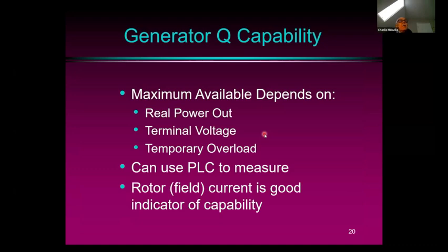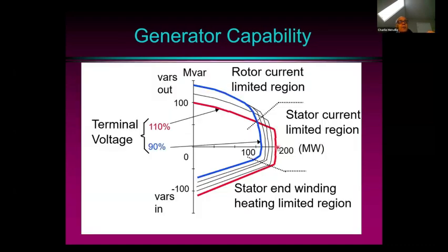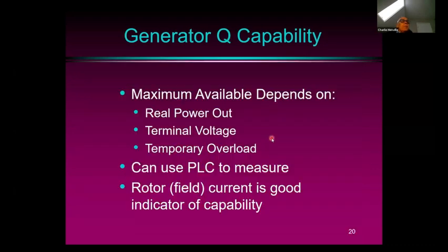So the maximum generator capability available depends on the real power output, as we saw previously. The higher the real power output, the less reactive power you can put out. It also depends on the terminal voltage, as I mentioned previously, and it usually has some temporary overload capacity. This would not be true of electronic power sources, but generators certainly can be overloaded temporarily to allow any other control actions to mitigate the overload problem. Programmable logic controllers find increasing application in power systems now, as they try to measure how close the generators are to their limits and take some control action to reduce the need for reactive power.